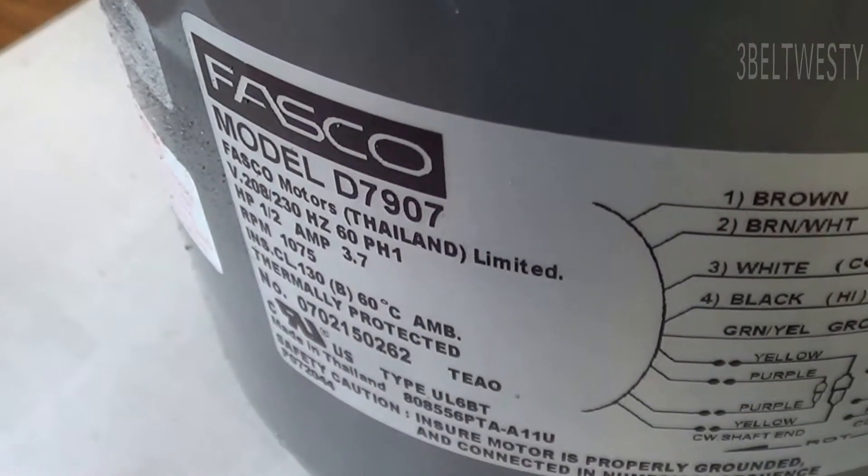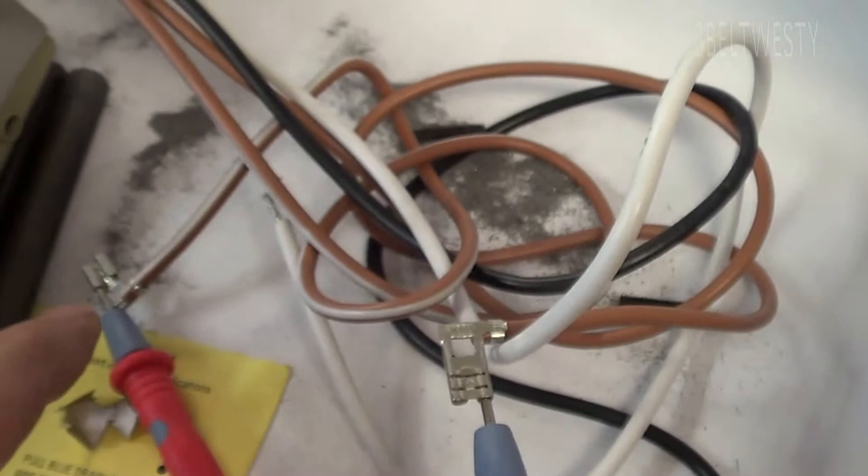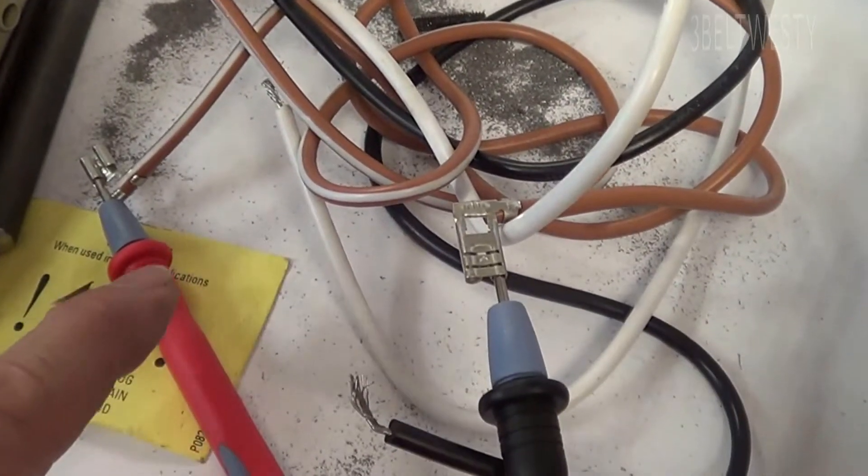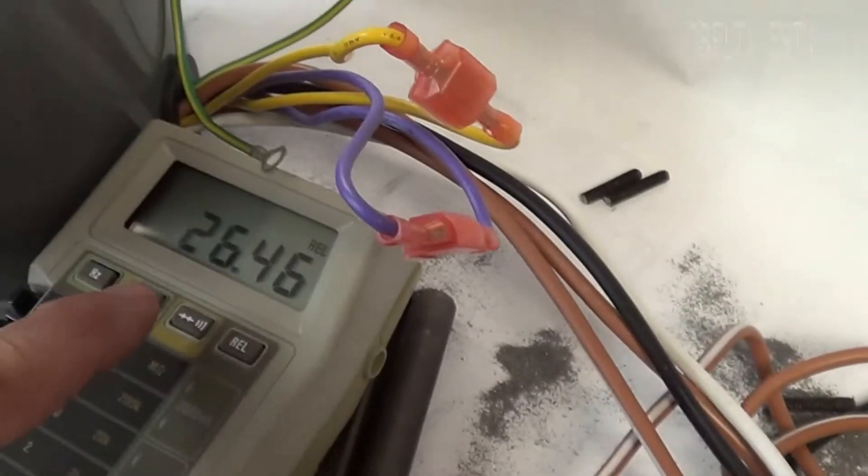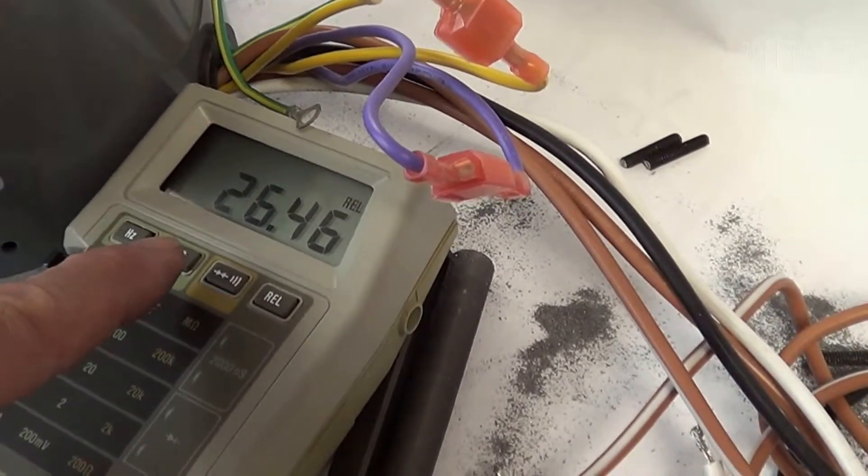Here's a Fasco D7907. Got an ohm meter across the two browns, about 26 ohms, and I've zeroed out the leads.